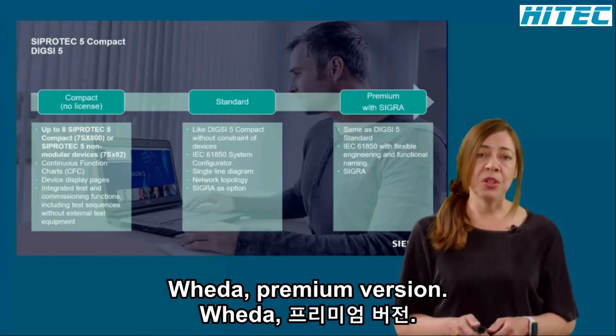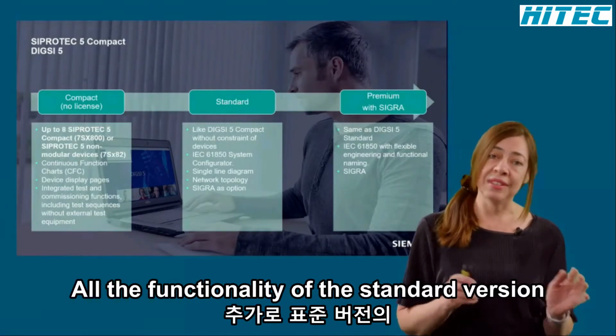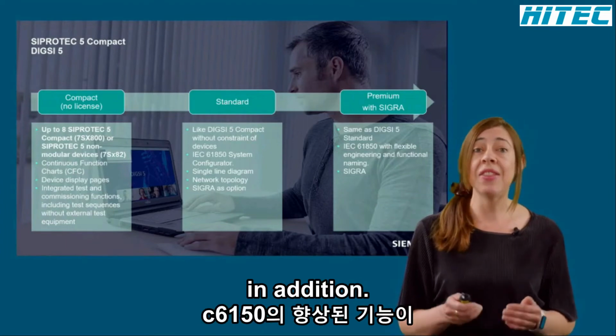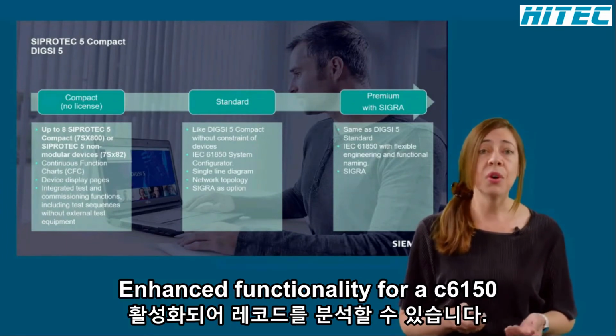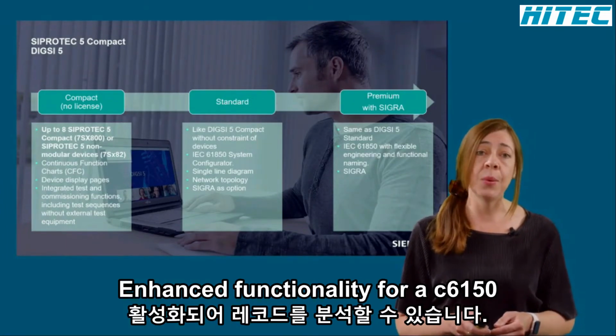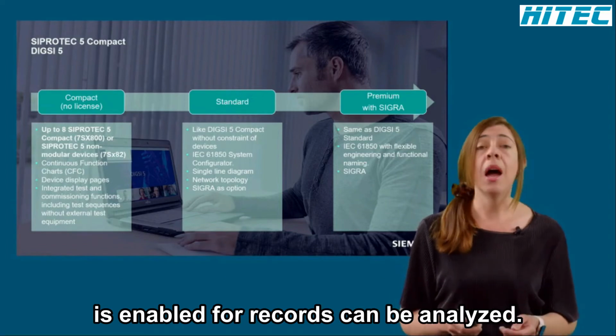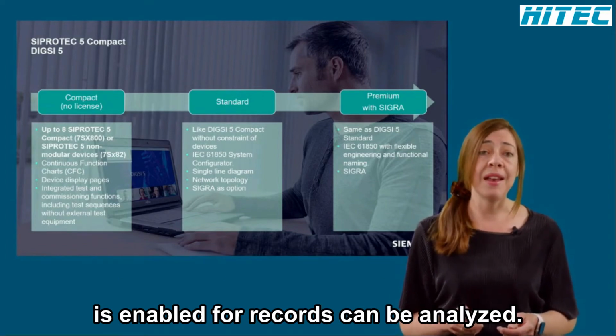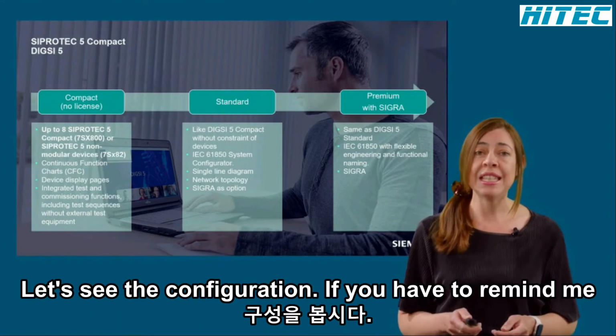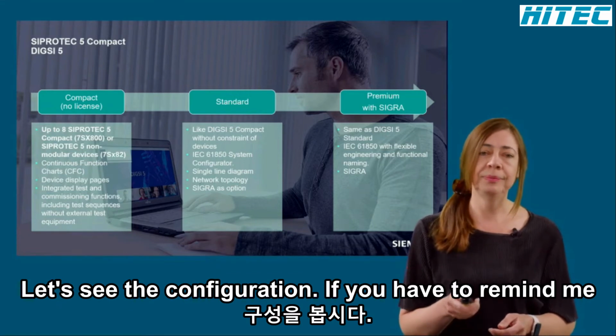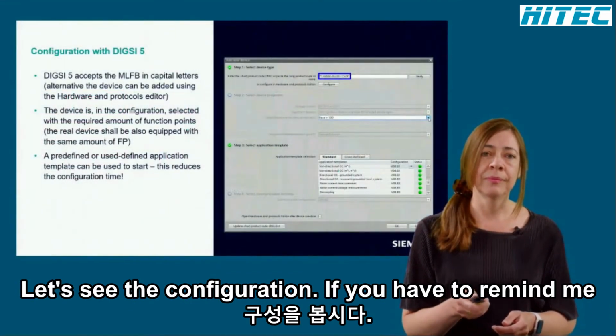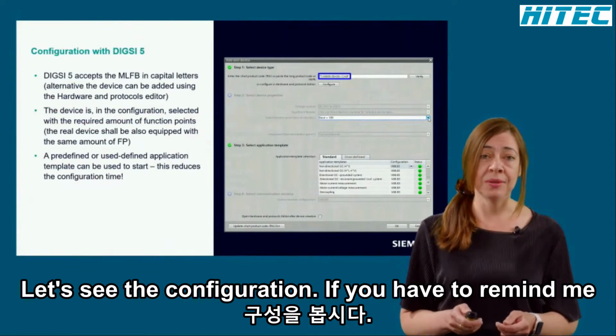With the premium version, all the functionality of the standard version is granted. In addition, the enhanced functionality for IEC 61850 is enabled, and fault records can be analyzed using the SIGRA software. So let's see the configuration.